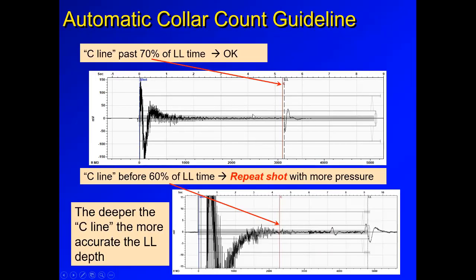and we'll see an example of applying a low pass filter. But basically, let's compare a low quality fluid level shot to a good quality fluid level shot. So we said, as the collar line is close to the liquid level line, then the software was able to identify collars almost all the way down. But some shots will look like this, where the C line is far from the liquid level line. If the time to the liquid level is 100% of your distance, the C line is about what, 45% of the distance to the liquid level. So this is even less than 60%. We recommend to have a collar count that is 70 or maybe 80% of the total number of collars.